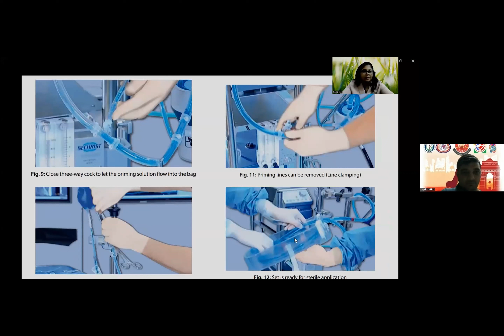So understanding this in a step-by-step manner, you open the pump head and check for signs of damage before priming. You attach the tubing bridge to the pump outlet and clamp the pump outlet tubing. This is done to ensure pump quality and the preparation for the priming. Then you attach the prime drainage line from the priming set to the pump inlet and tilt the pump and outlet upwards. Remove the clamp from the pump inlet and, using the clamp on the outlet, ensure an air-free prime of both the pump and the outlet tubing. Reclamp the end of the outlet tubing when complete.